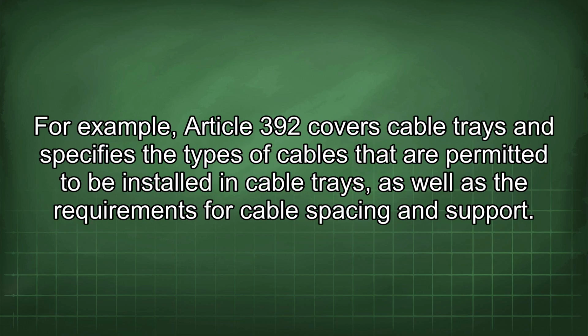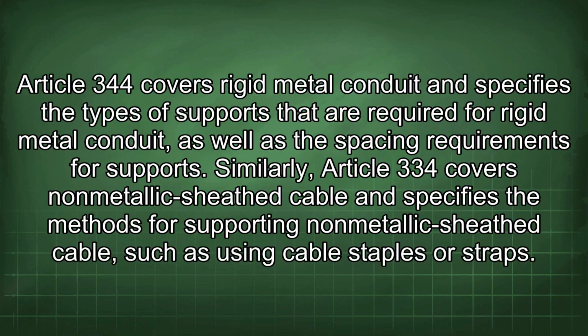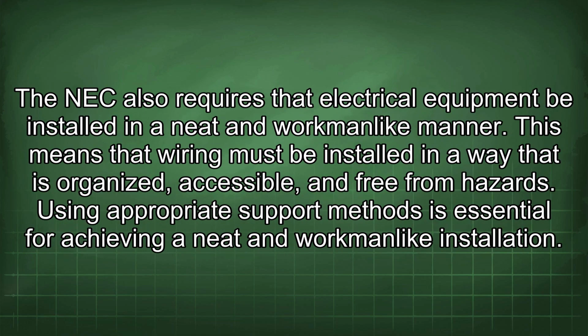For example, Article 392 covers cable trays and specifies the types of cables that are permitted to be installed in cable trays, as well as the requirements for cable spacing and support. Article 344 covers rigid metal conduit and specifies the types of supports that are required for rigid metal conduit, as well as the spacing requirements for supports. Similarly, Article 334 covers non-metallic sheath cable and specifies the methods for supporting non-metallic sheath cable, such as using cable staples or straps. The NEC also requires that electrical equipment be installed in a neat and workmanlike manner. This means that wiring must be installed in a way that is organized, accessible, and free from hazards. Using appropriate support methods is essential for achieving a neat and workmanlike installation.